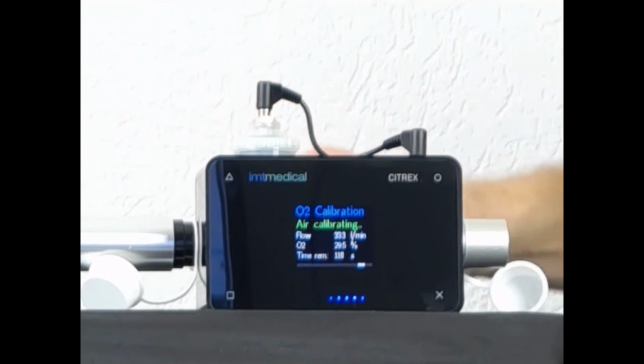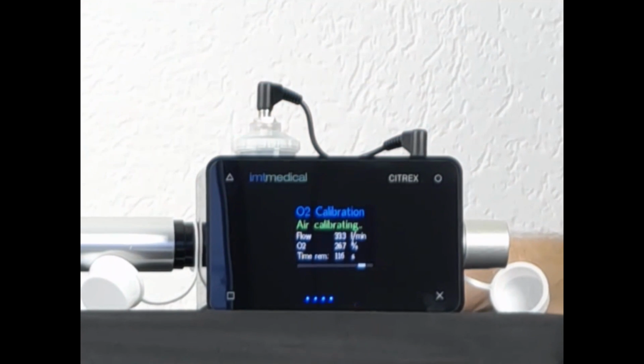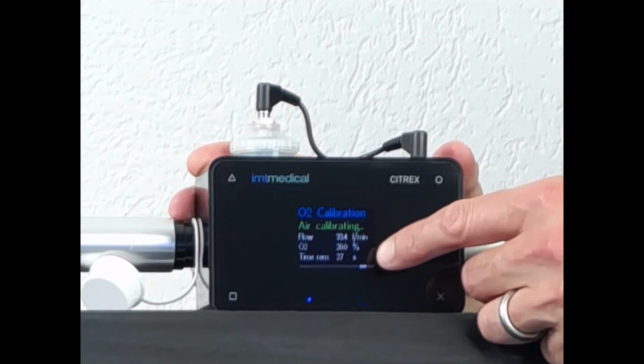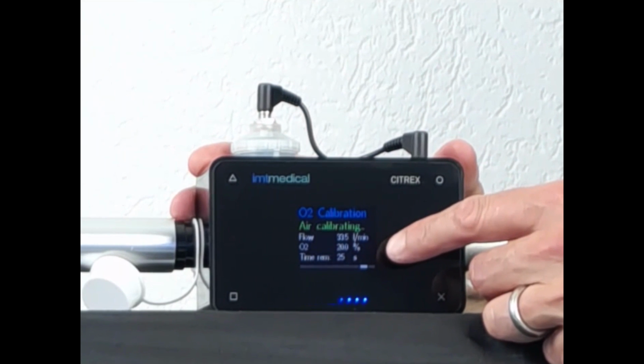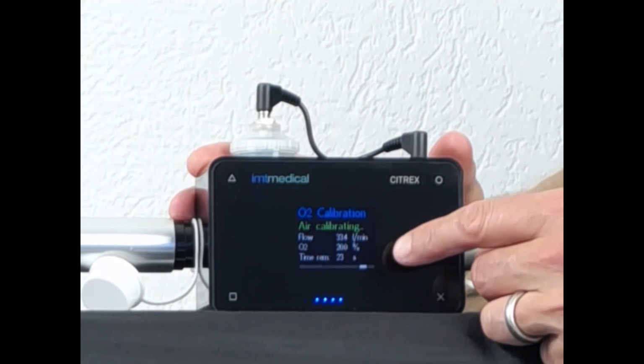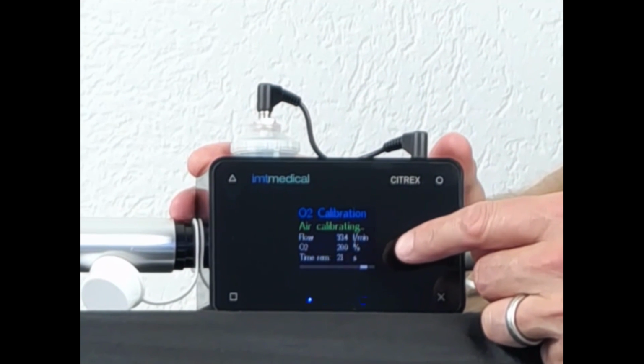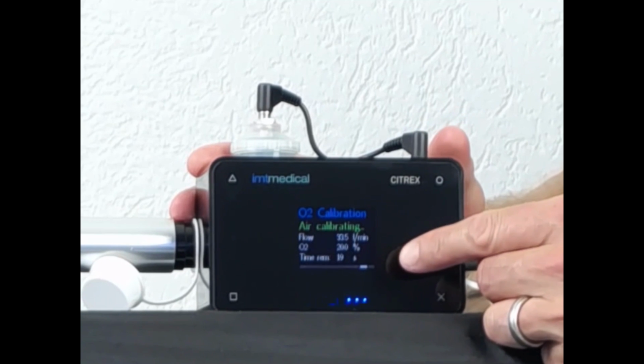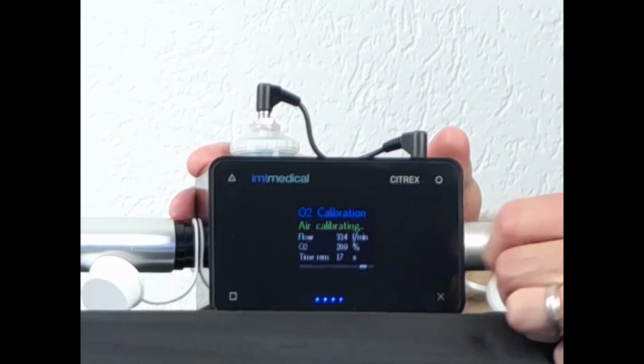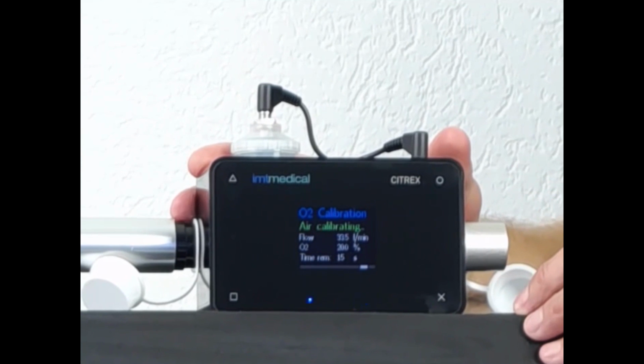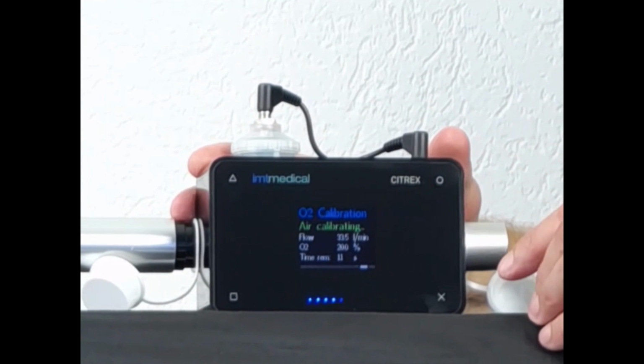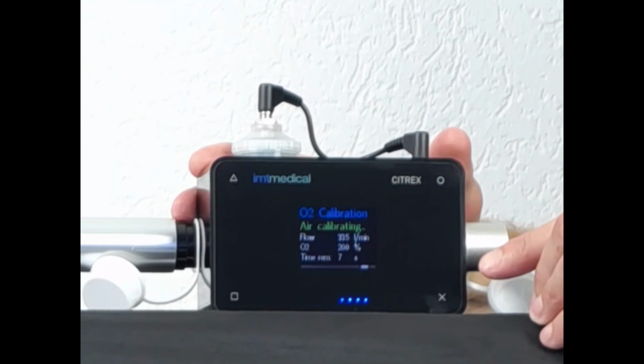Again, this is going to take 2 minutes, during which the sensors are averaged. So we have 25 seconds of oxygen sensor calibration left. The second point was 21% oxygen, which is normal air. And after this, my oxygen sensor is calibrated and ready for measurement. I repeat, this oxygen sensor calibration should only be done once a week or before very important oxygen measurements.